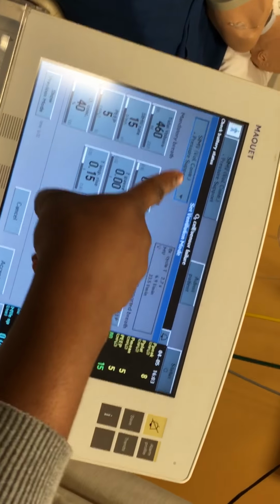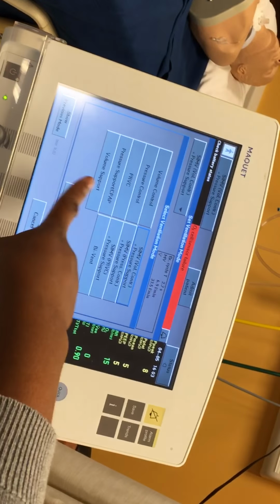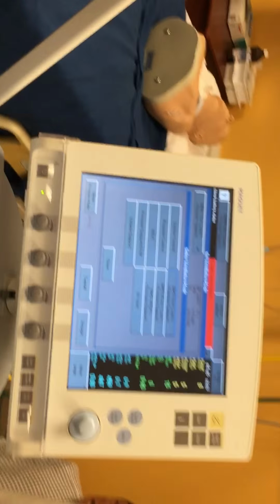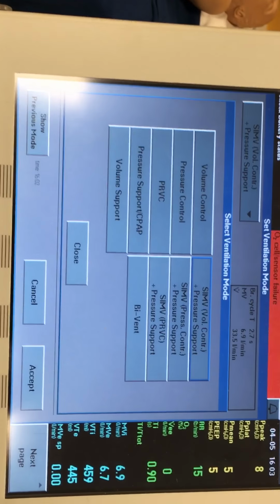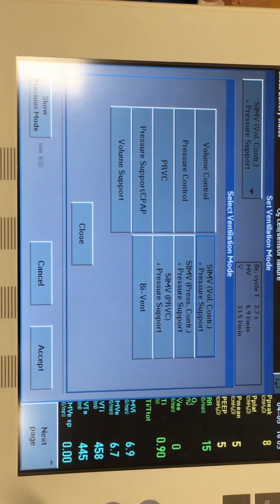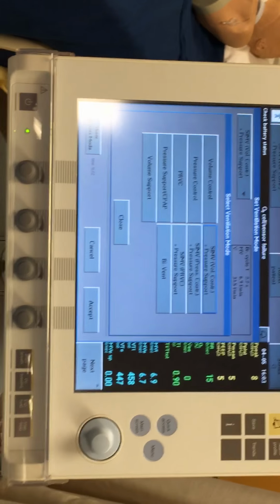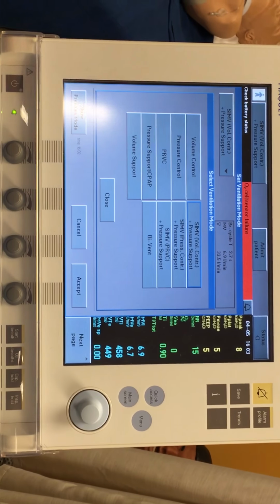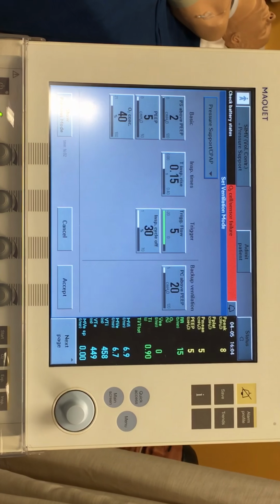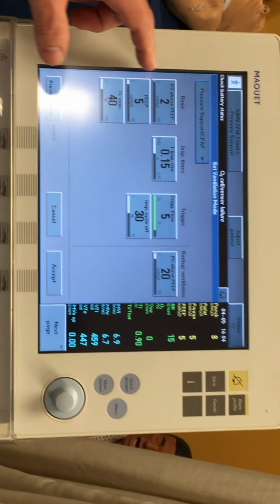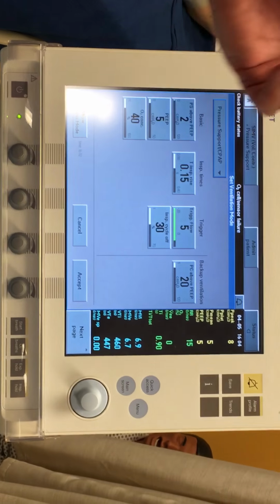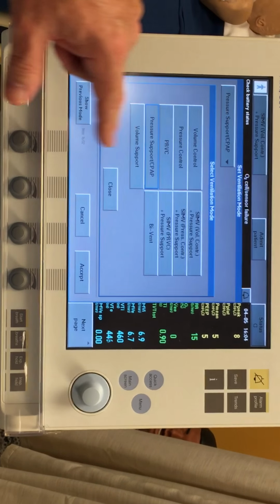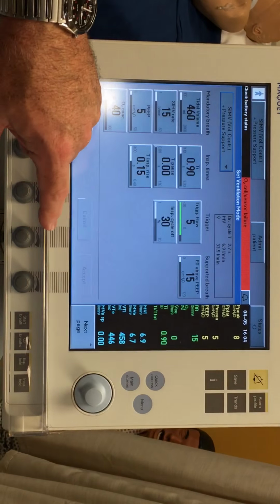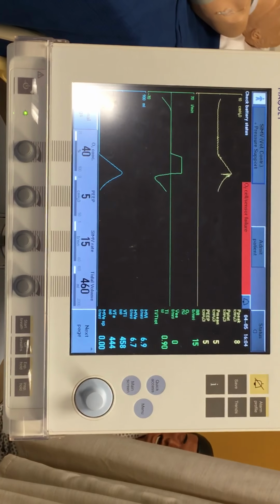So when we are on this ventilator, we'll go through all of these modes. Nope, we'll just give you, I think your skill checkoff says volume SIMV is the mode you're going to use. Now, if the patient's breathing fine and I'm weaning them off, and I want them to do all the spontaneous breathing on their own, I'll hit pressure support. I have my pressure support, my CPAP, my FiO2, and my trigger. That's how I put them in pressure support CPAP, which sometimes you hear people refer to as just spontaneous.